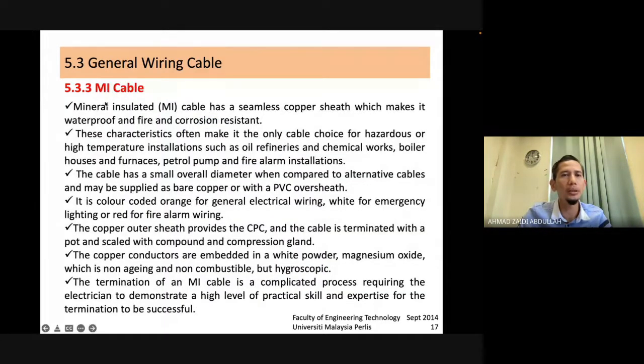Okay, another type of cable is the MI cable. MI refers to mineral insulated. It has a seamless copper sheath which makes it waterproof, and fire and corrosion resistant. This cable is very expensive. This characteristic often makes it the only cable choice for hazardous or high temperature installations such as oil refineries, chemical works, boiler houses, furnaces, petrol plants and fire alarm installations. So if your project is related to some of these types of project, you must use MI cable.